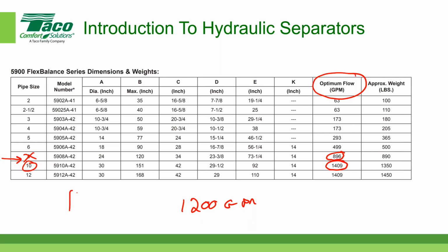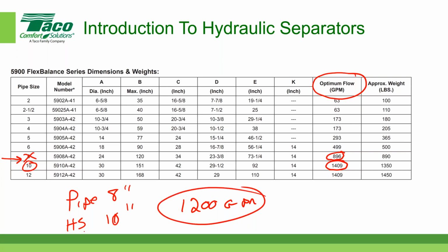So even though the pipe, put that note here, the pipe is 8-inch, the hydraulic separator is actually going to be a 10-inch because we have to have enough to maintain this 1,200 gallons per minute. So to answer Mario's question earlier, is it based on flow or size? You actually have to look at this chart and make the appropriate selection based on the flow in gallons per minute.